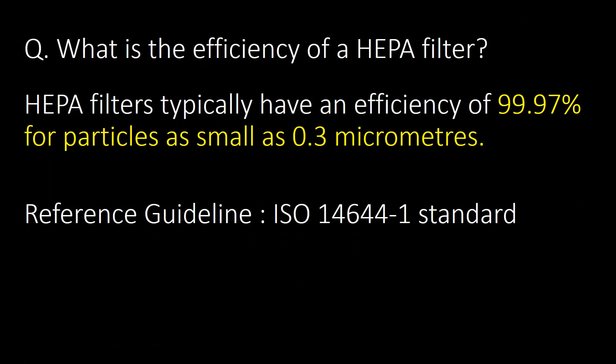What is the efficiency of HEPA filters? HEPA filters typically have an efficiency of 99.97% for particles as small as 0.3 micrometers. Reference guideline: ISO 14644-1 standards.